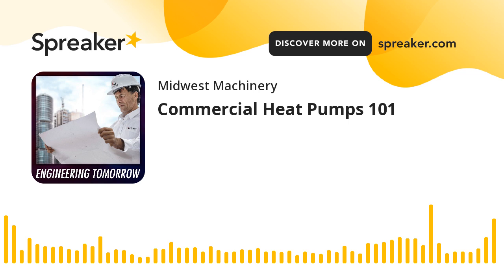They also keep spare parts, compressors of every size, maybe a fan motor of every size, maybe a coil of every size in case one springs a leak. But like any other piece of equipment, over the years you're going to have some kind of replacement or parts that need to be replaced, but not any worse than any other type of equipment. The difference between a water source heat pump and a large chiller, though, is significant. Most building operators don't know how to repair a chiller compressor, which could be 500-600 tons. That's a very large and complex piece of machinery, whereas it's pretty easy to swap out a compressor or a fan motor, relatively speaking.